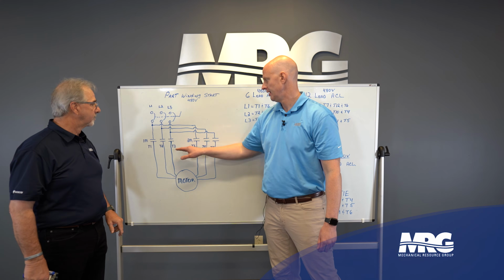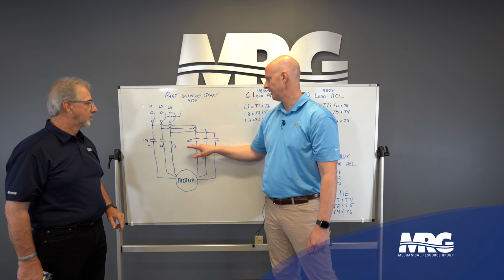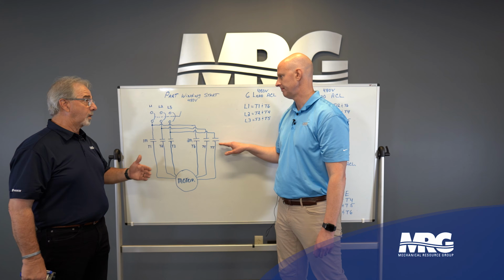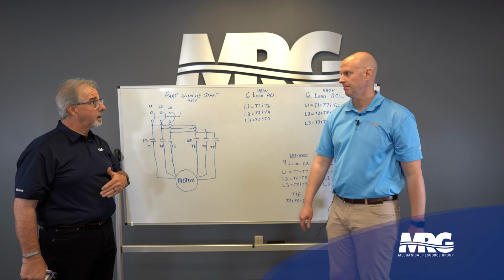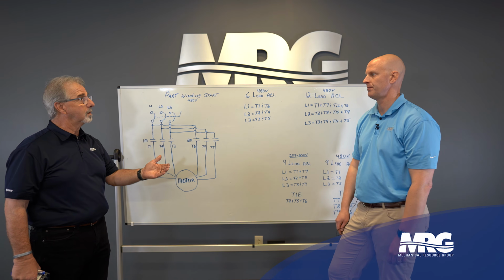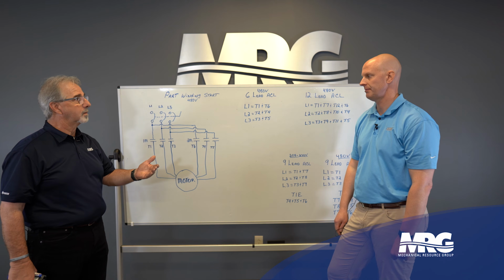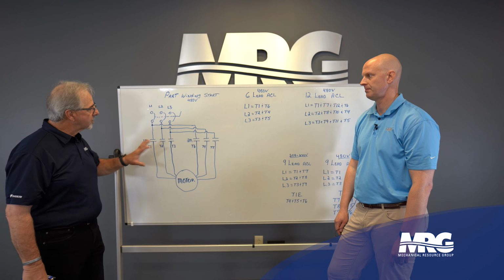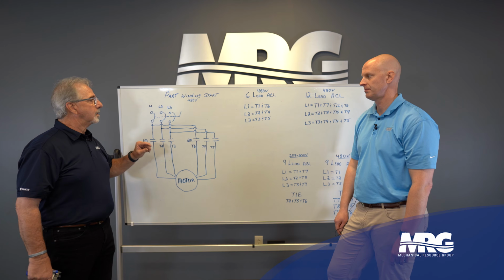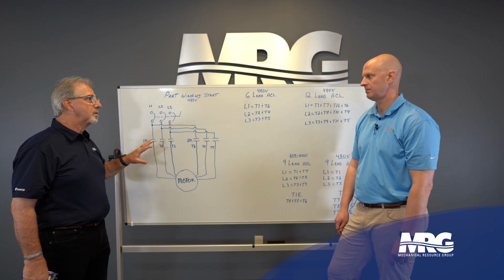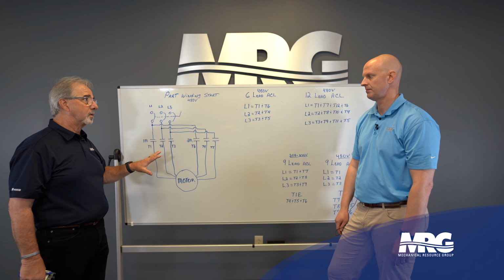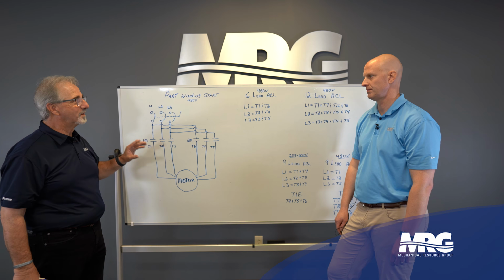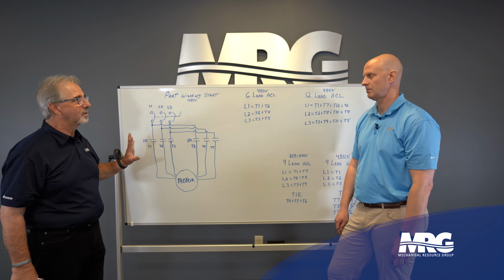Motor windings. These are going to come on, and there's going to be a timer, and then 2M is going to come on. Right, and then we bring in the rest of the winding. That gives me full torque, full current. So this is what we call part winding start. Now what's important is that you can do either 6-lead motors or 12-lead motors. When it gets into 12-lead, it gets a little more concerning.